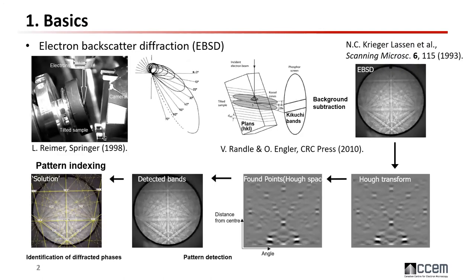EBSD stands for electron backscatter diffraction. As you can see from this schematic, when your electron beam arrives on a well-polished sample which is highly tilted to 70 degrees, your backscatter diffraction will be projected onto your EBSD camera. After that, the diffraction pattern will be indexed by software using a lookup table, so that you can do either crystal orientation mapping, strain mapping, or even phase identification.